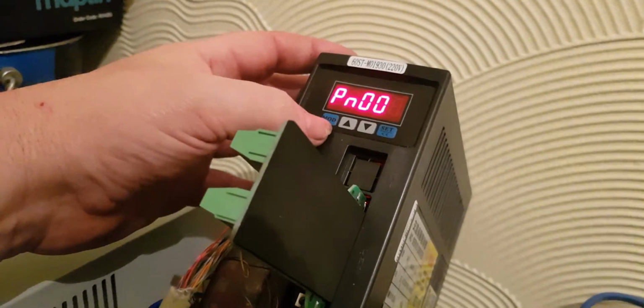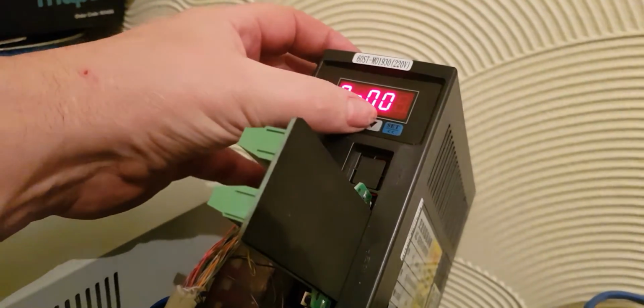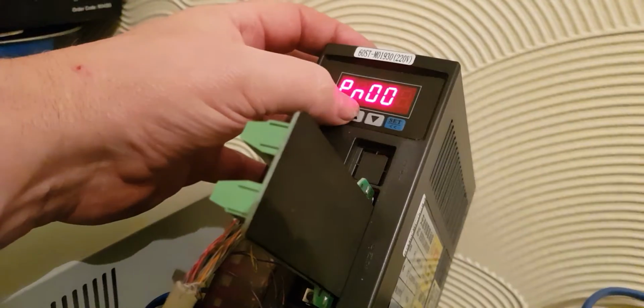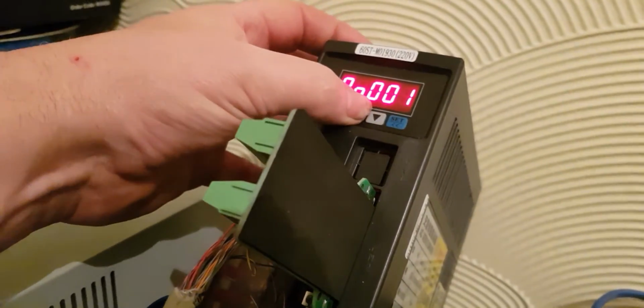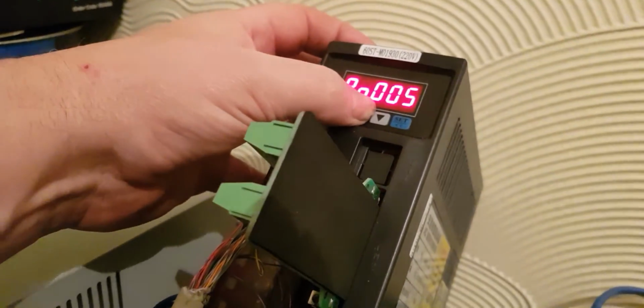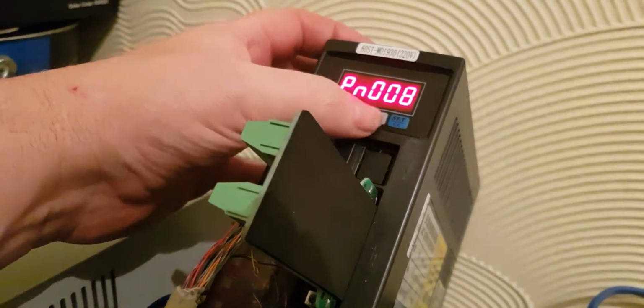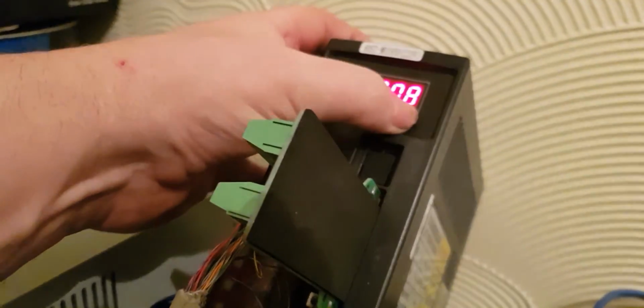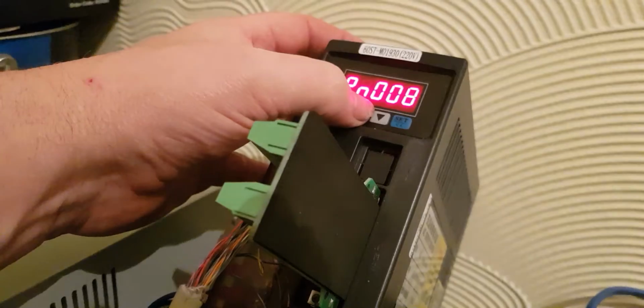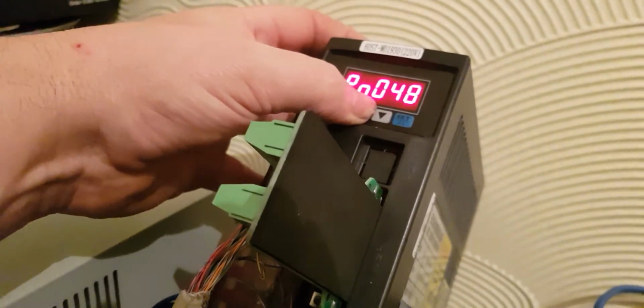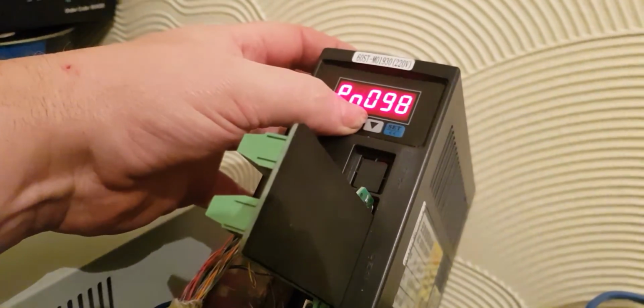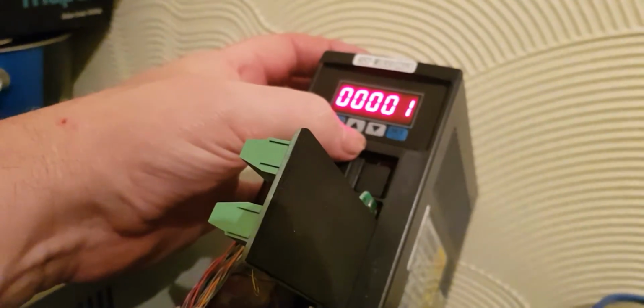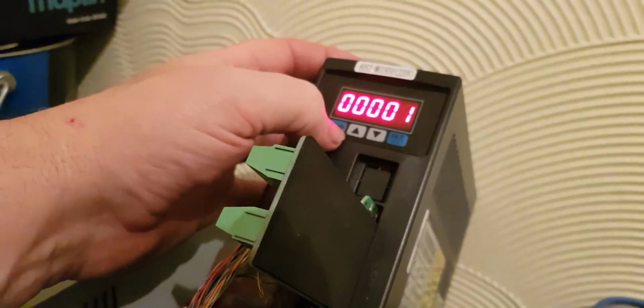So we want to change the parameter 98, and you use the up and down keys. You can see the digits flashing. The first digit, we're going to put 8 in there. Use the set key to jump. One click and it jumps across the digits. 98. Then you hold the set key in for a few seconds and release it. And now you enter into the parameter.